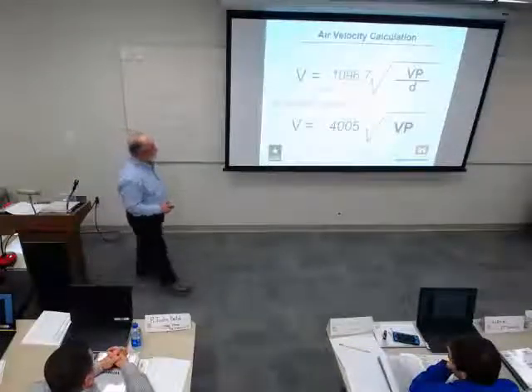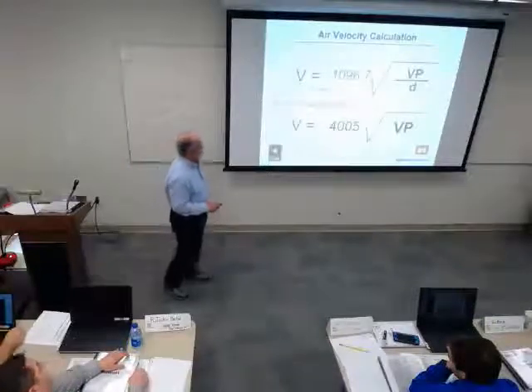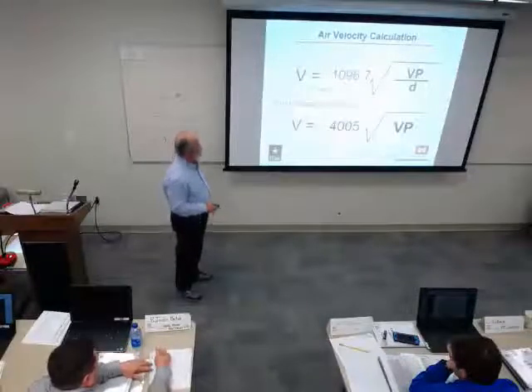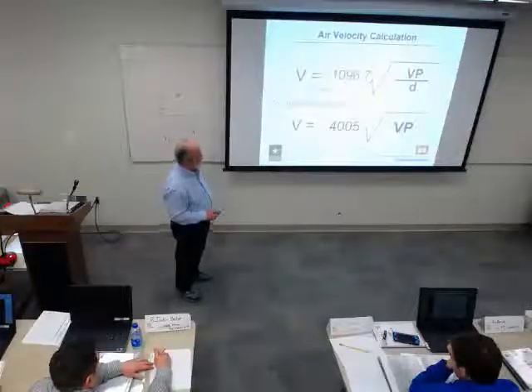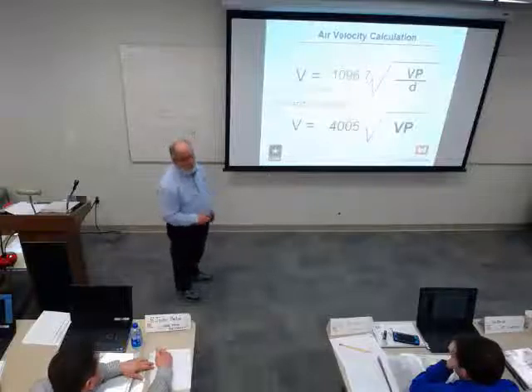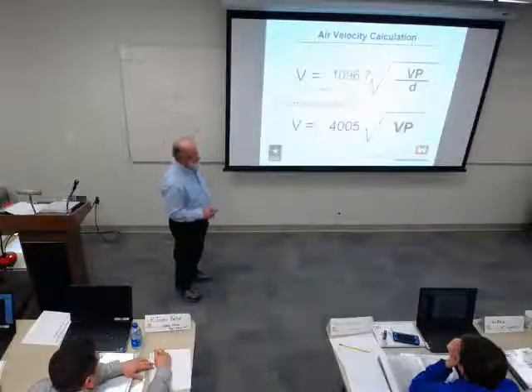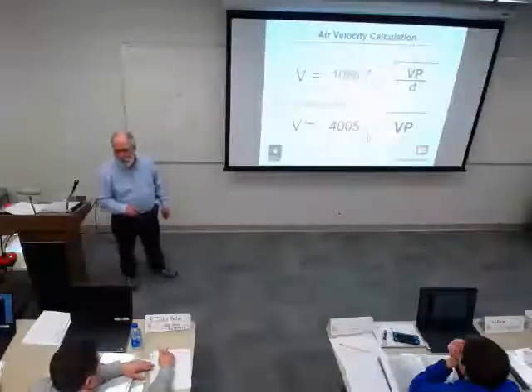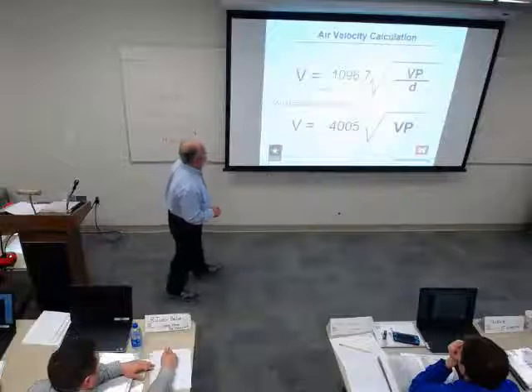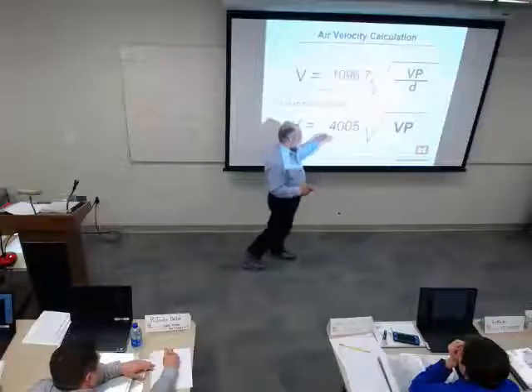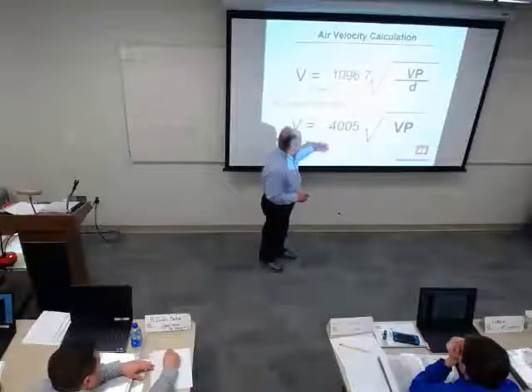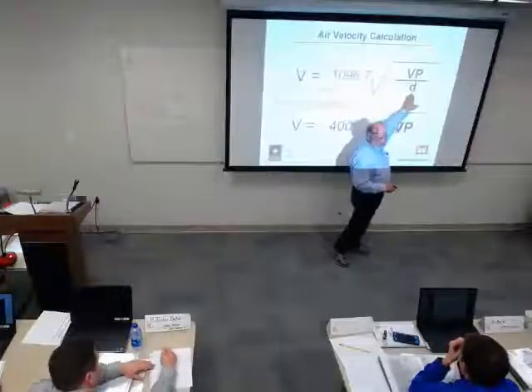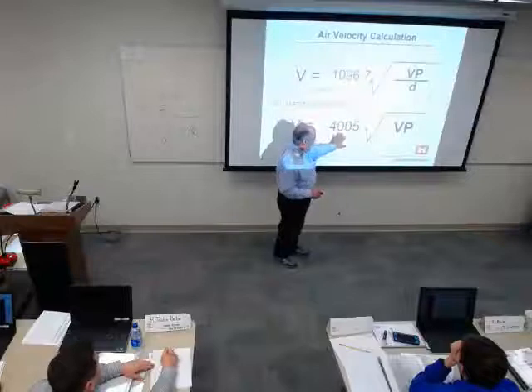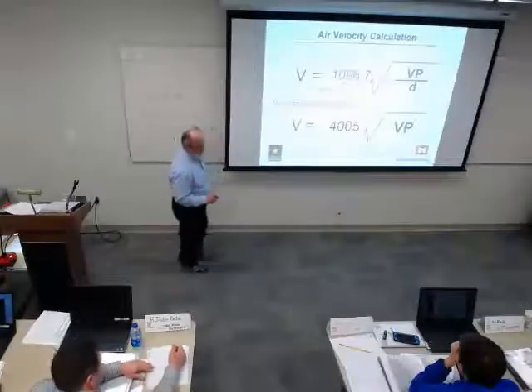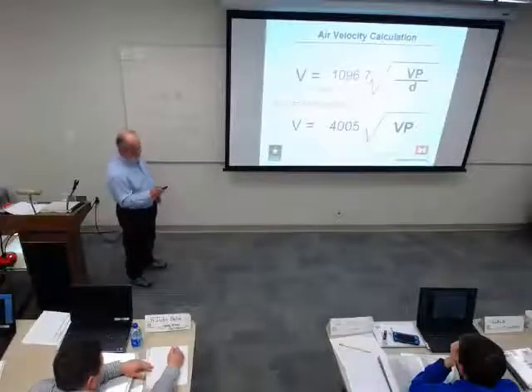So here's the equation that's used for calculating the velocity. That's equal to that number times the square root of the velocity pressure, in inches, divided by the density of the air. So the density comes into play here. Normally what's used is standard conditions, we'll talk about standard in a minute. In standard conditions, if it's always the same condition, that D is always the same. So for standard conditions, we have 4,005 times the square root of the velocity pressure. That's typically what's used, but as you can see, density plays into that.